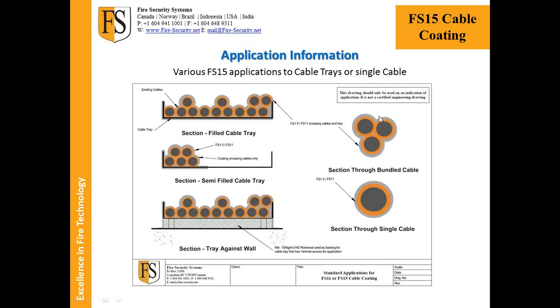If it is on the floor, how do we get it underneath it? There's no need. You've got concrete there. That cable is actually sitting on possibly 1 millimeter of surface area. Okay. So maybe the base of that high voltage cable is not getting coated at that base point of 1 millimeter. And without oxygen as well. So there's basically no feed of oxygen for any flame to spread at that base point. Yeah, understood. When you're looking at a trefoil situation, you are simply coating the outside of the cable once again.